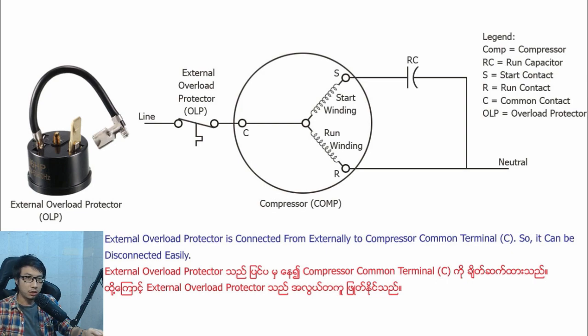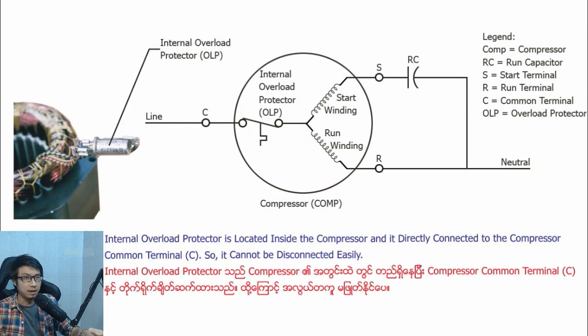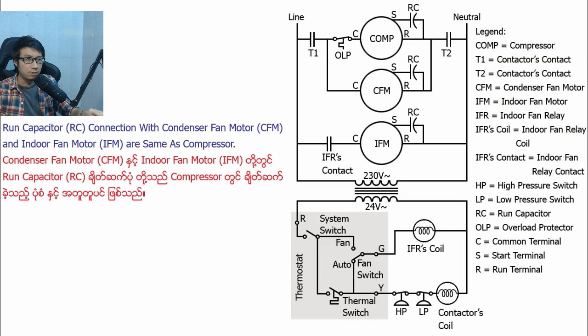The overload protector protects the compressor from overload and overheat. The overload protector is connected to the compressor common terminal. The overload protector is located inside the compressor and is directly connected to the compressor common terminal, so it cannot be disconnected easily. Run capacitor connections with the condenser fan motor and indoor fan motor are the same as for the compressor.